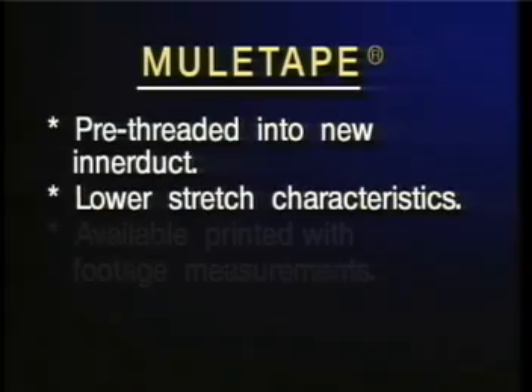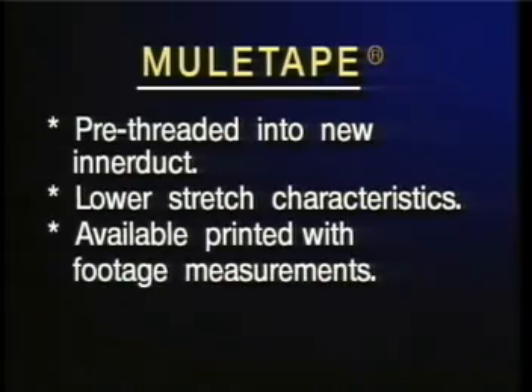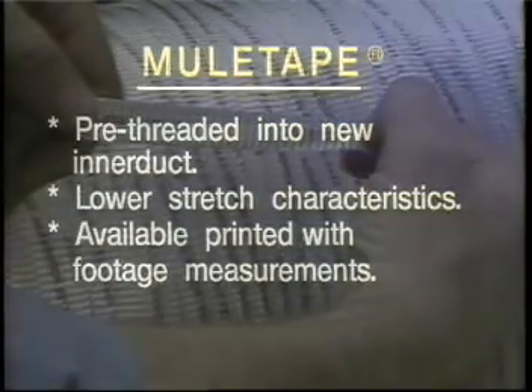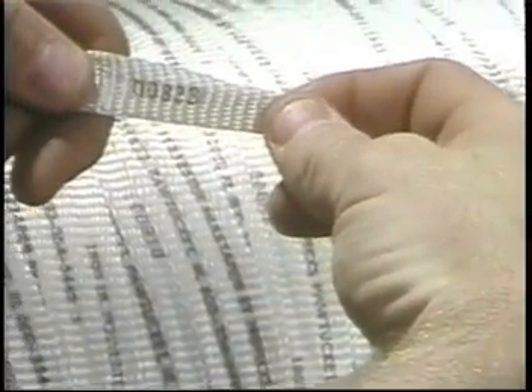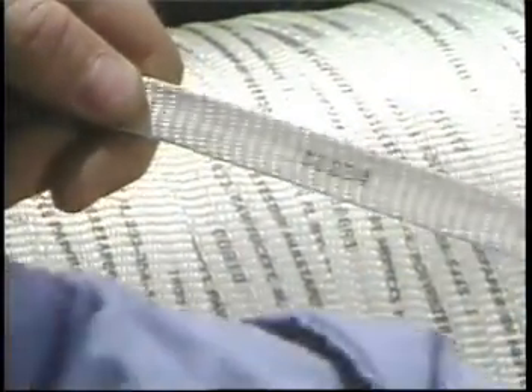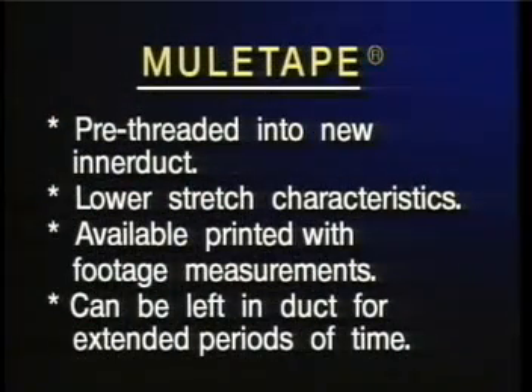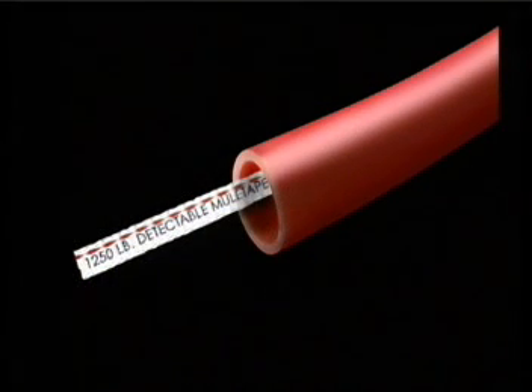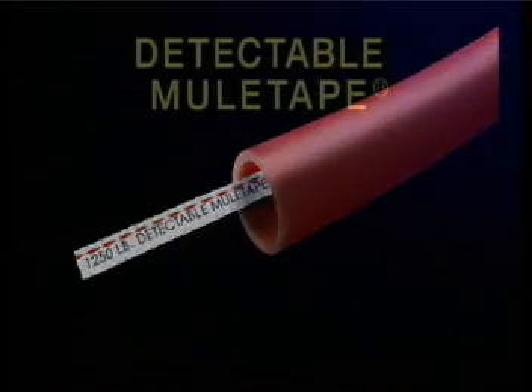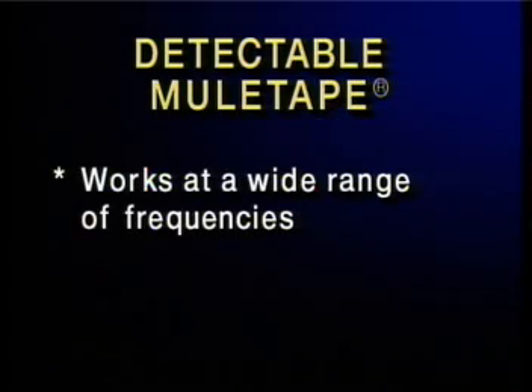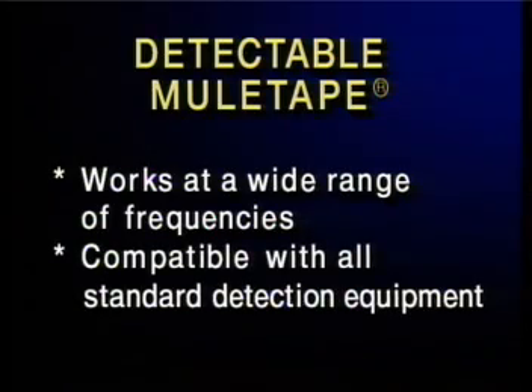Muletape is available printed with footage measurements, so you'll know exact conduit measurements, where the cable is at any point during the pull, and how much tape is left on a partial roll. Muletape can be left in a duct for extended periods of time and still retain all of its pulling strength. And with detectable Muletape, you can locate the duct quickly and easily. NEPTCO's detectable Muletape works at a wide range of frequencies and is compatible with all standard detection equipment.